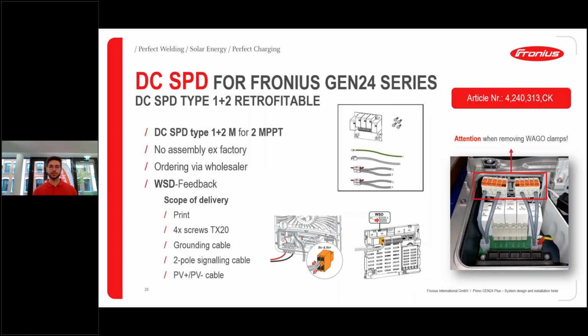Okay, so that's it for the topic of backup solutions. However, there are some more options available for this product, and one would be the surge protection device, and this can be integrated into the device, the Primo GEN24. It's called DC SPD Type 1 and 2, and it's a print-based version. So like we can see here, the actual SPDs are soldered onto a print board, and it can be mounted in the connection area, like we can see in the picture at the right.